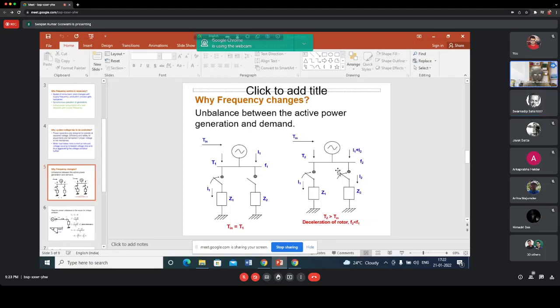It cannot change instantly, and for changing the input, some actions must be taken - those actions must first be sensed. So what will happen? If the input remains fixed, input torque remains constant, but output torque increases, there will be a deceleration of the generator. Then the speed will decrease, meaning the frequency of generation will decrease. So when the load increases, the immediate effect is a reduction in frequency.